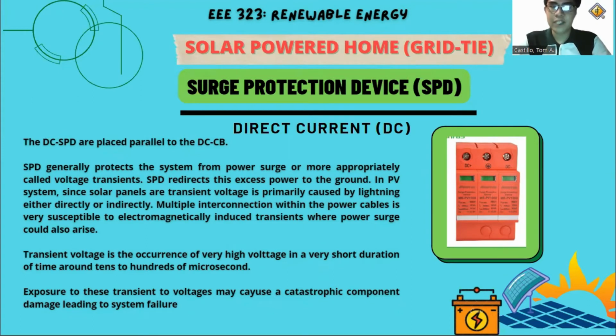The DC SPD is placed parallel to the DC circuit breaker. An SPD generally protects the system from power surge, or more appropriately called voltage transients. SPD redirects this excess power to the ground. In a PV system, since solar panels are exposed, transient voltage is primarily caused by lightning, either directly or indirectly. Multiple interconnections with the power cables are very susceptible to electromagnetically induced transients, where power surge could also arise. Transient voltage is the occurrence of very high voltage in a very short duration of time, around tens to hundreds of microseconds. Exposure to this transient voltage may cause catastrophic component damage leading to system failure. So the surge protection device protects the system against the transient voltage.